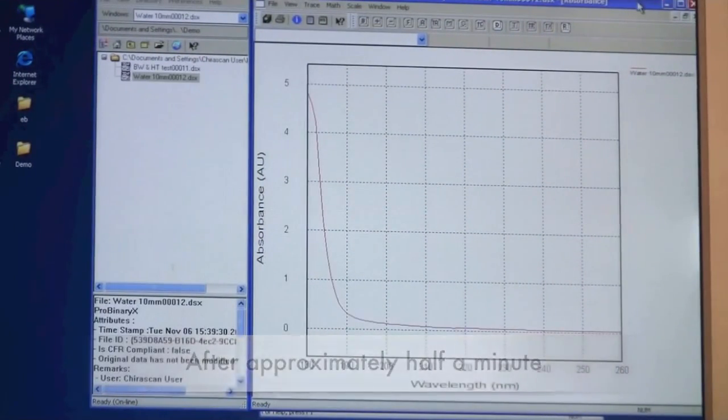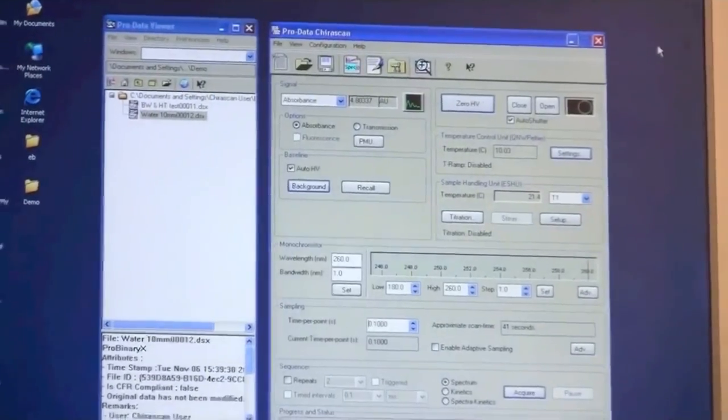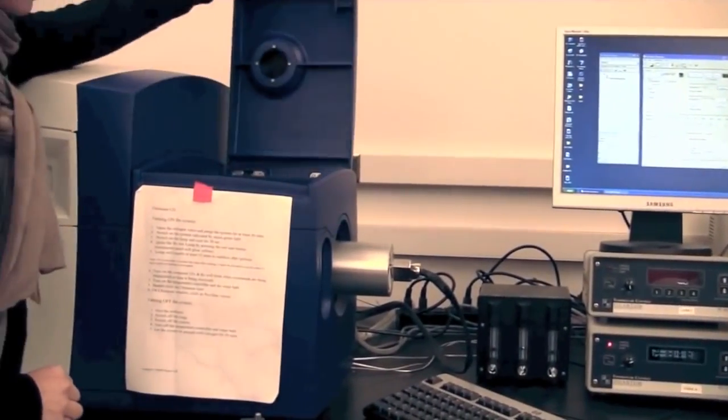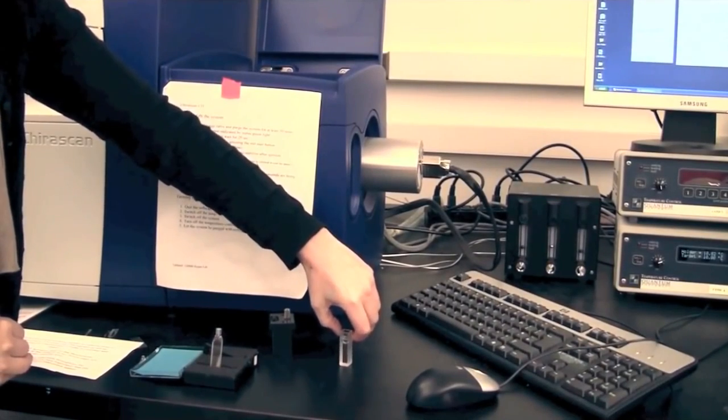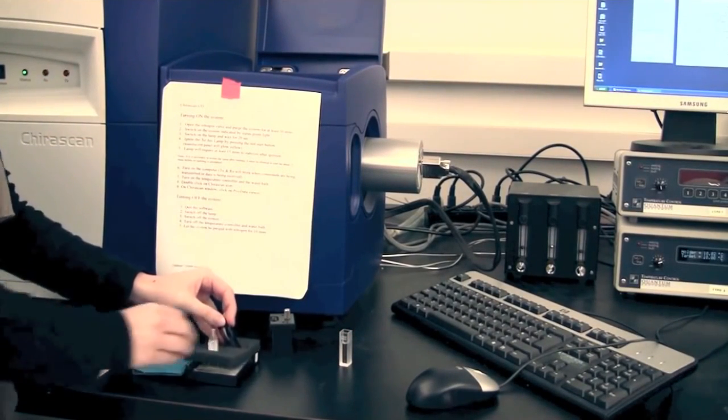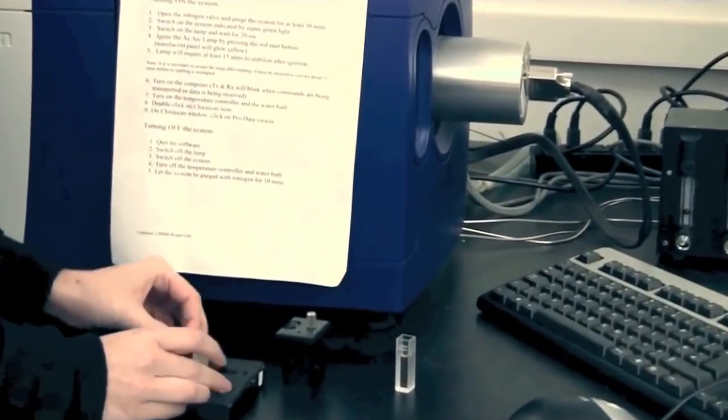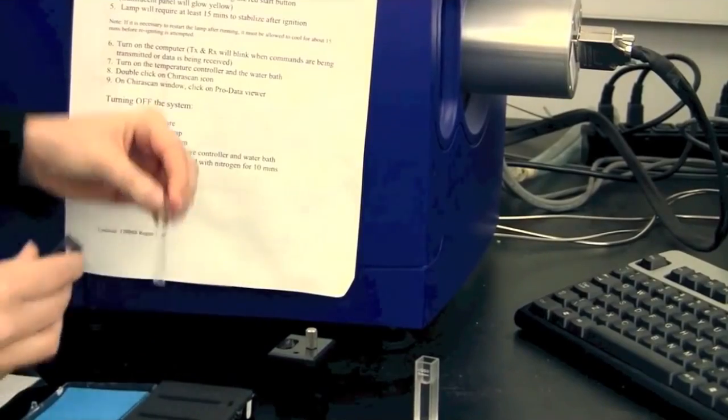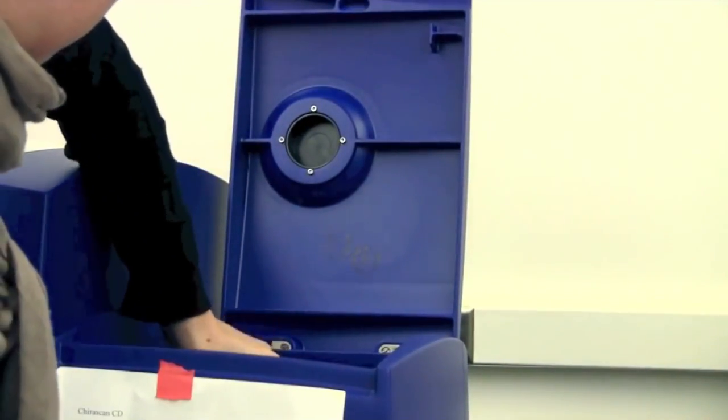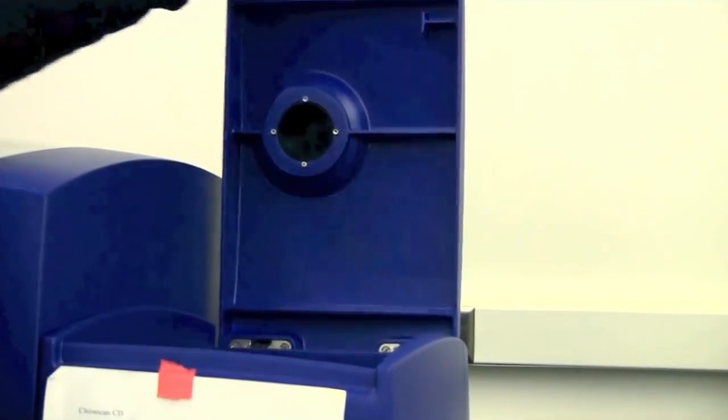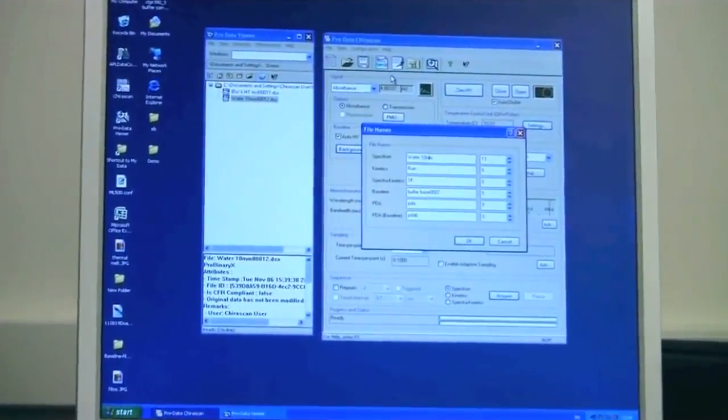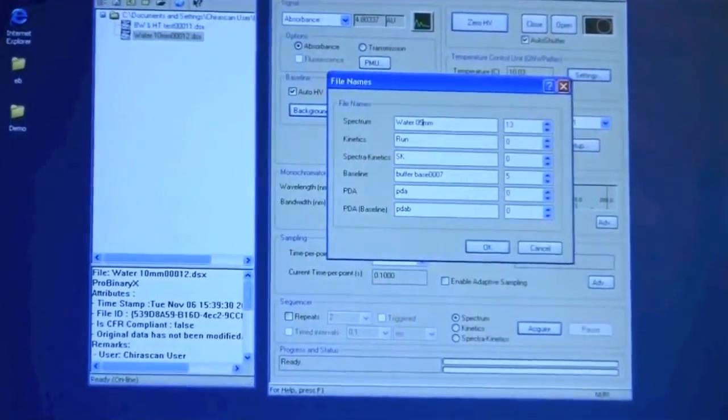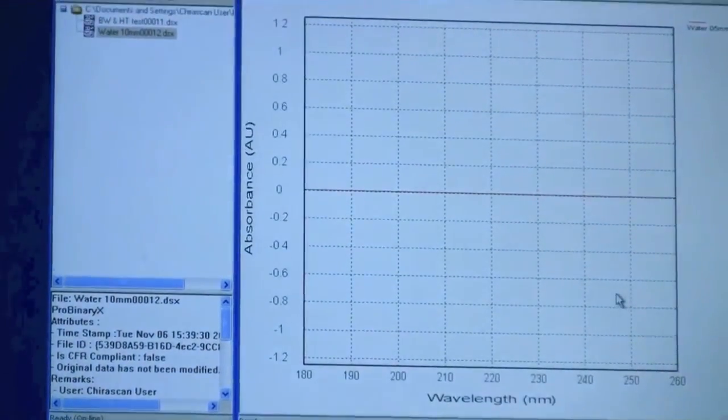After I have collected my 10 mm traces I will close the window and I will change the cuvette to be the short path length instead. Take out my 10 mm path length. When you are using smaller size cuvettes you have either the option of using a different cuvette holder or you can use a spacer like this. Now I will use the spacer for this one. I will then rename the file so I know which file is which and I will collect a trace for the short path length.